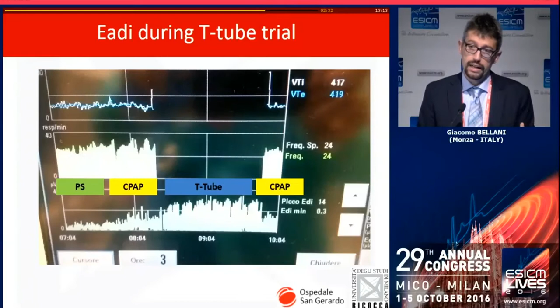And of course, the work of breathing, the EDI, goes up because the patient has to breathe more. But then we remove also PEEP, we put the patient on a T-tube, and look how much the breathing effort of the patient goes up. Maybe this patient had a cardiac failure, so for any reason, removing not support, but positive pressure, mean airway pressure, put the patient under distress, and as soon as we restore the CPAP by reconnecting the patient to the ventilator, you see that immediately peak EDI drops. So this is just a qualitative assessment of the evaluation of a patient, not even connected to a mechanical ventilator.